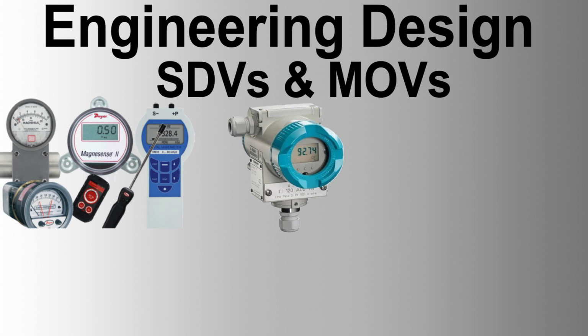Anti-corrosion measures. Protective compounds and durable coatings shall be used to prevent corrosion in case of water condensing inside the various housings, in addition to protecting external parts. Actuators shall be painted according to coating specifications. Nickel plating may be used for the inside surface of cylinders to provide resistance to wear and corrosion. This shall be an electroless coating technique with a minimum thickness of 75 microns. The underlying surface material shall be treated to provide corrosion resistance.